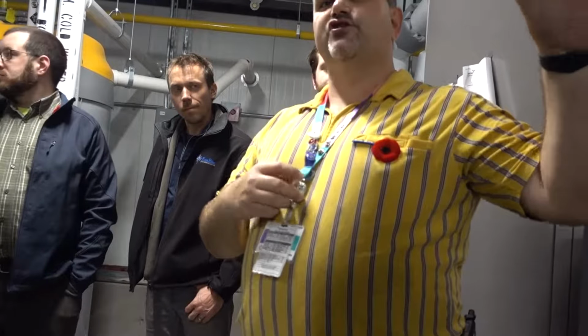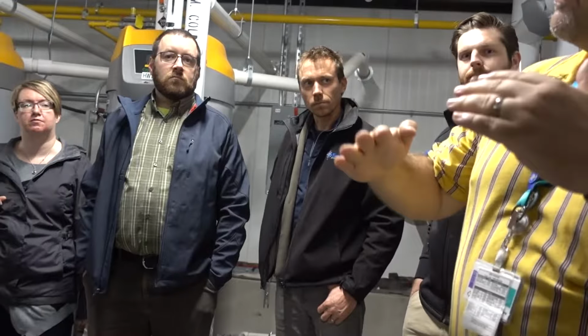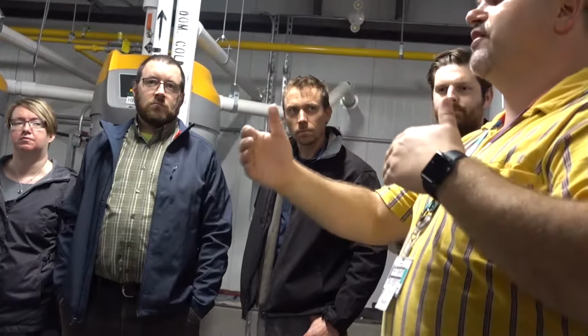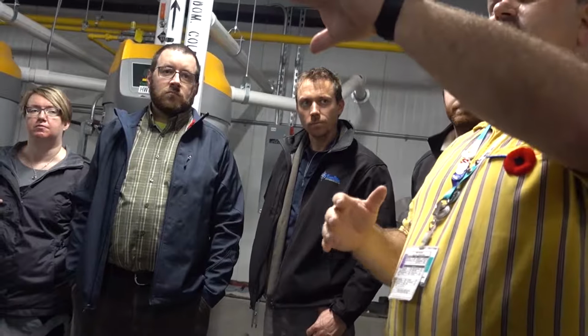By having those heat exchangers rather than feeding the cooling loop back here, we smooth out the curve. Geothermal is a very powerful system, but you don't want it to change. You don't want big rates of rise or big cooling loads, right? You want everything to stay fairly stable. And to do that, we have the big heat exchangers here so that the delta on the cooling loop from when it goes out to when it comes back should be very stable, right? This way we can heat up the water, cool down the water in the looping here much more drastically in a shorter period of time than what we send out into the building.